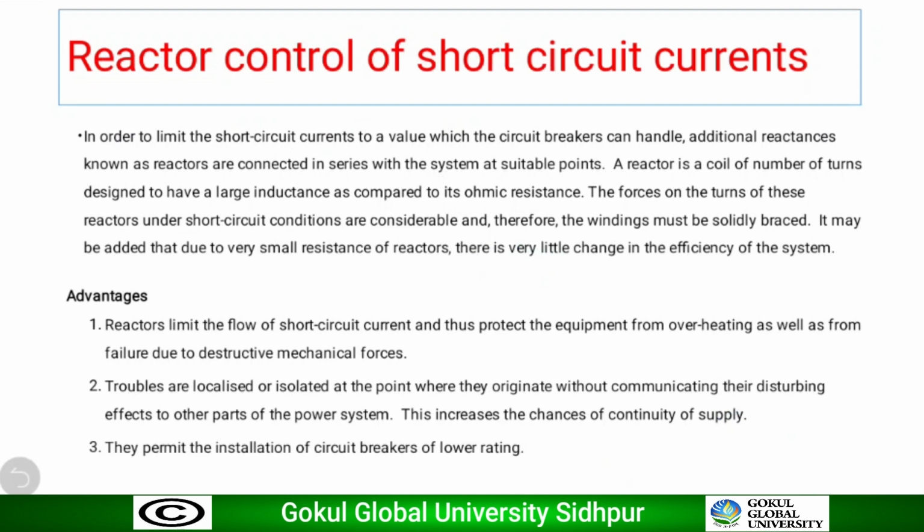A reactor is a coil of a number of turns designed to have a large inductance as compared to its ohmic resistance. The force on the turns of this reactor under short circuit condition is considerable and therefore the winding must be solidly braced. It may be added that due to the very small resistance of the reactor, there is very little change in the efficiency of the system.